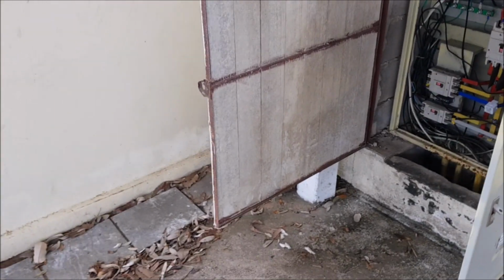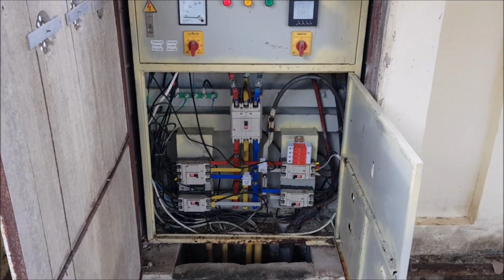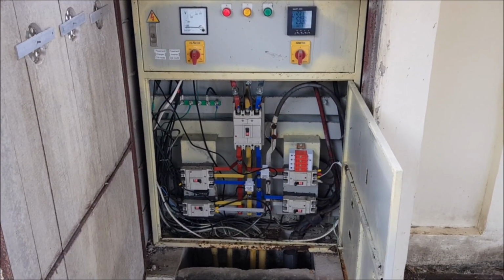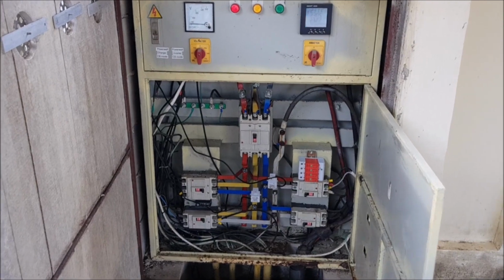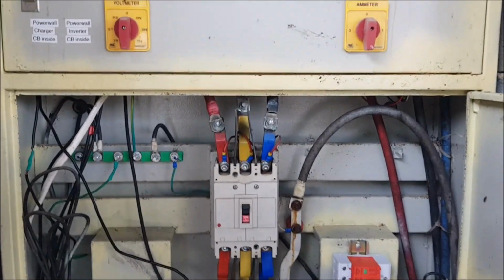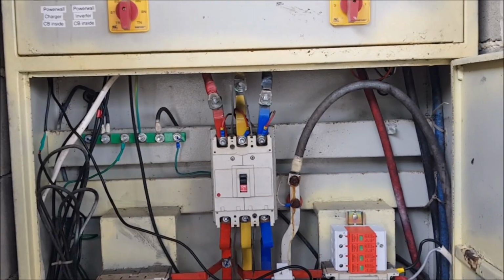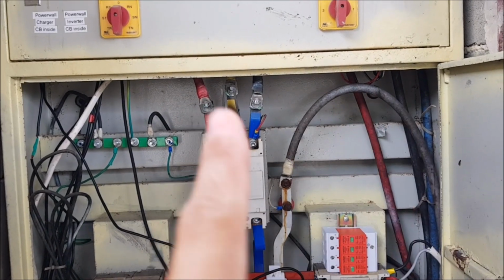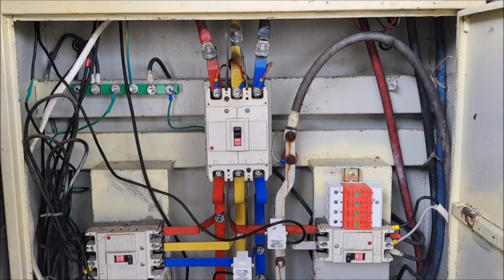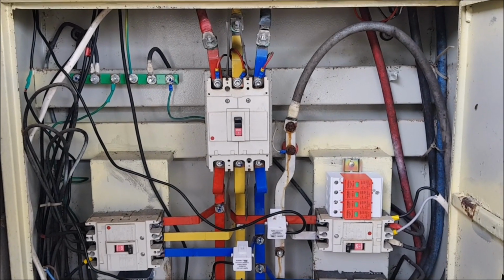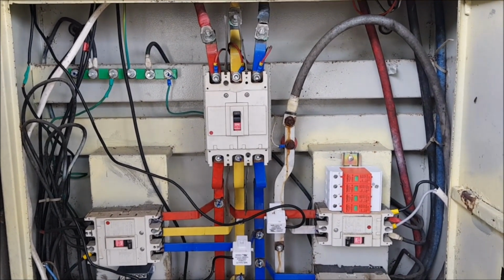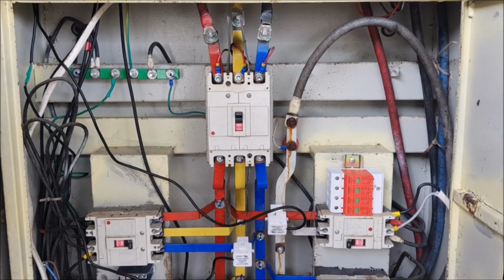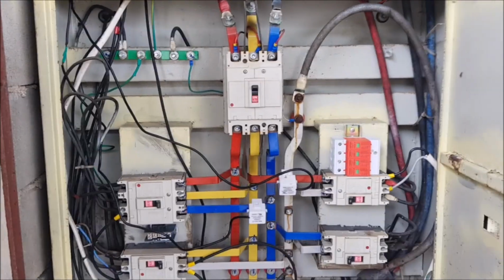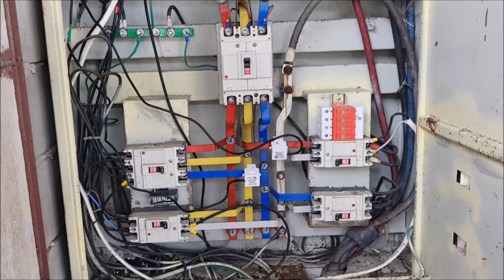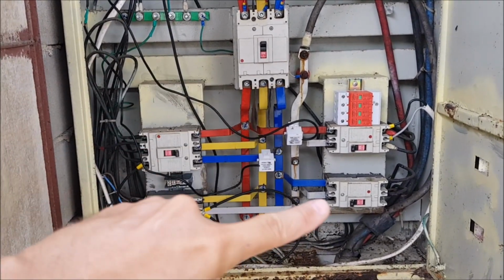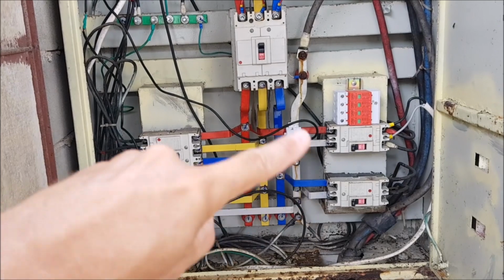But let's talk about the main distribution board. This is actually the first distribution right after the transformer. The transformer comes in here via these very big cables, and the first thing it meets is the main breaker. It's a three-phase 250 amp breaker, and what that breaker is doing is protecting the next portion of the distribution, which would be this inner core here.